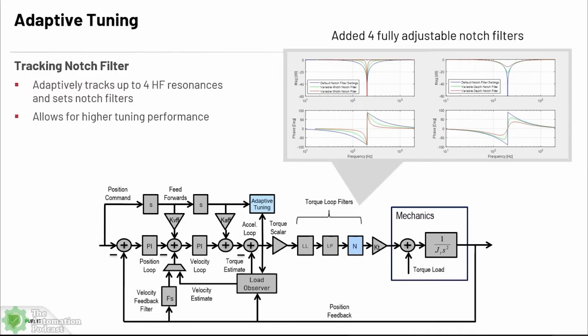We do this with four high-frequency tracking notch filters, which automatically find the four highest resonant frequencies and set themselves to them. The easiest way to understand this is like noise-canceling headphones—same concept, canceling out that high frequency noise—and that's exactly what adaptive tuning does inside the drive control.